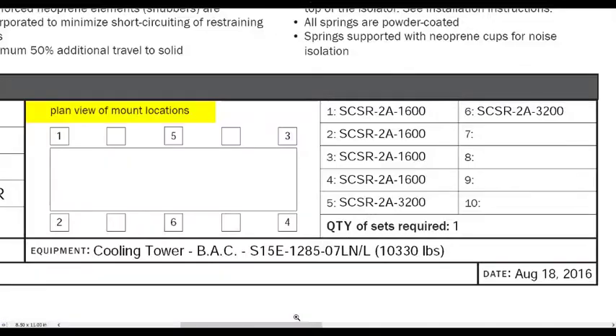But before we leave this page, one more very important thing is the plan view of mount locations. This graphic shows which isolator goes where on the equipment. With induced draft cooling towers like this one, it is common to see the center of gravity in the geometric middle, so the isolators will be the same in the corners, shown here in positions 1, 2, 3, and 4.